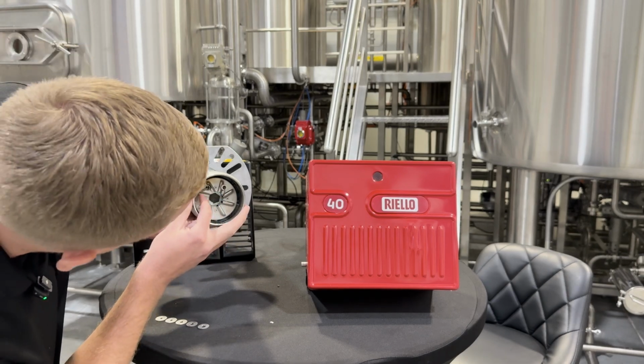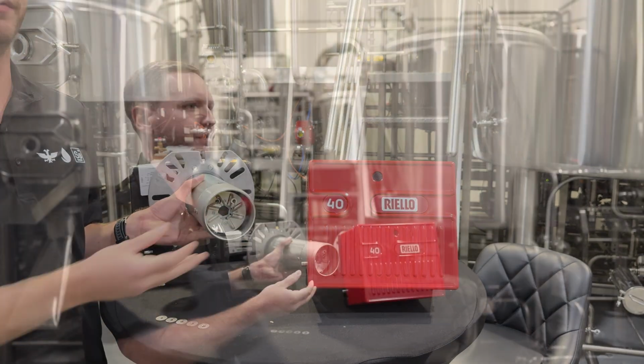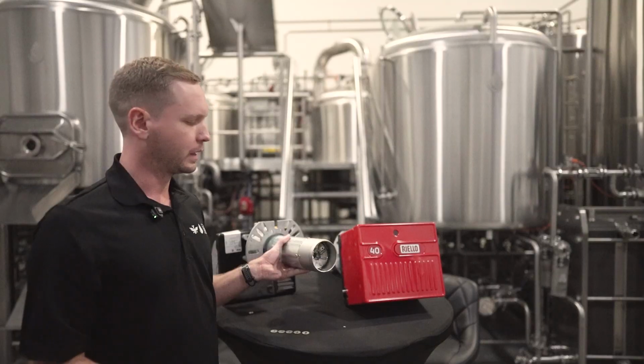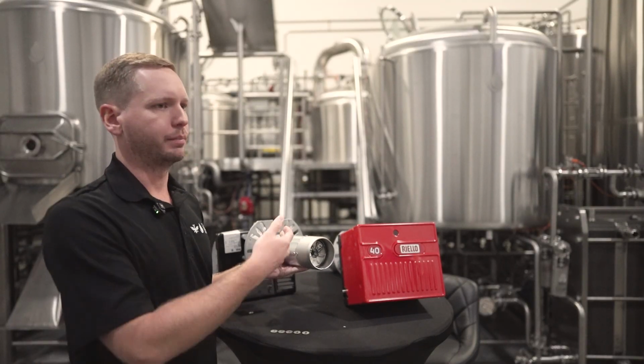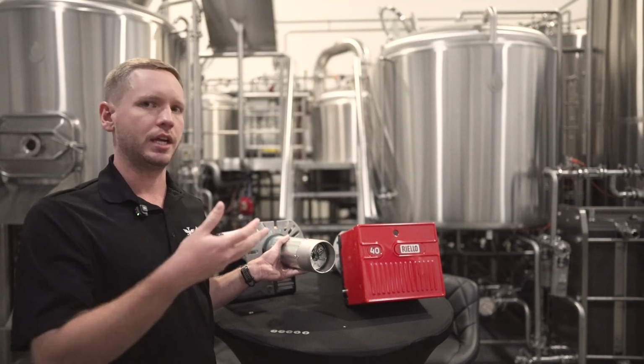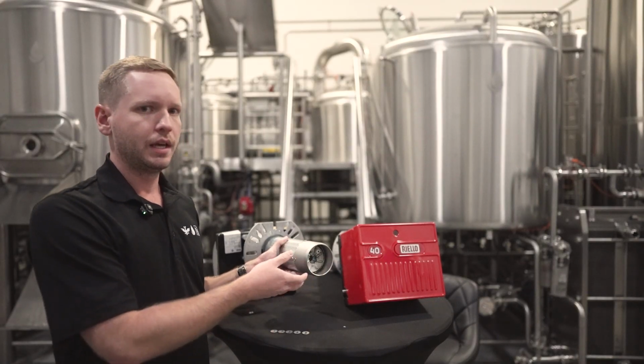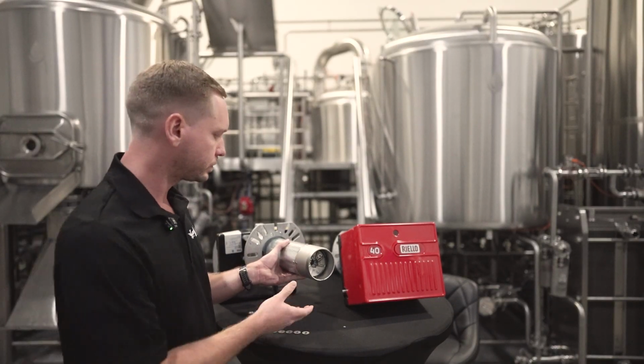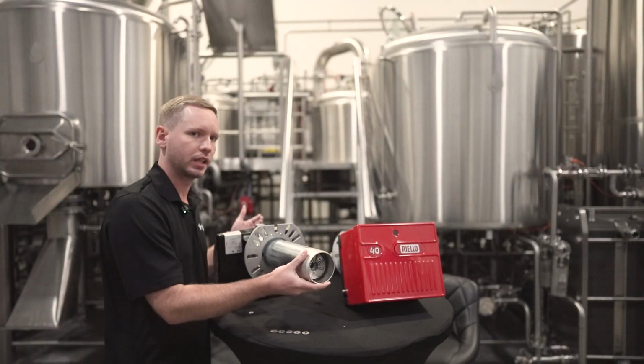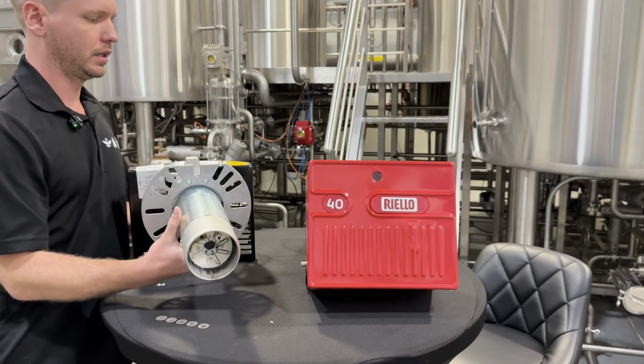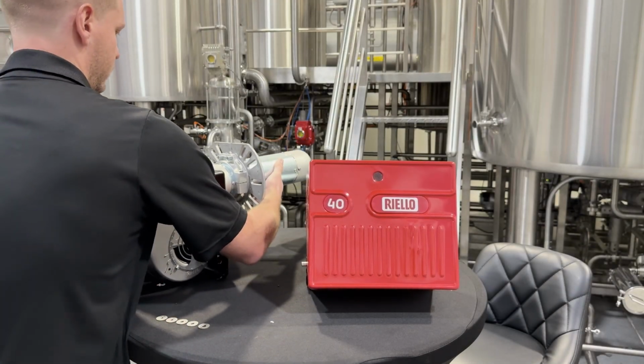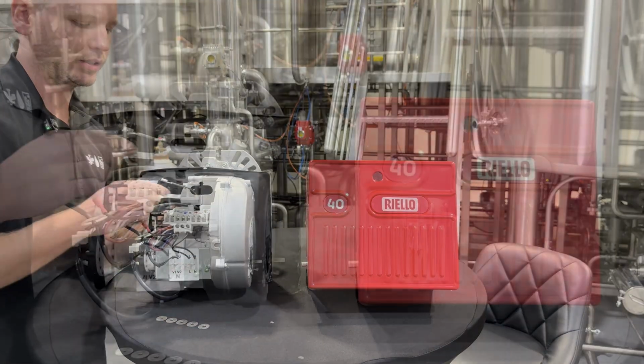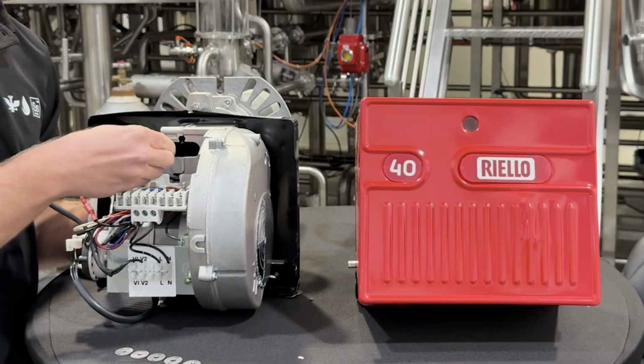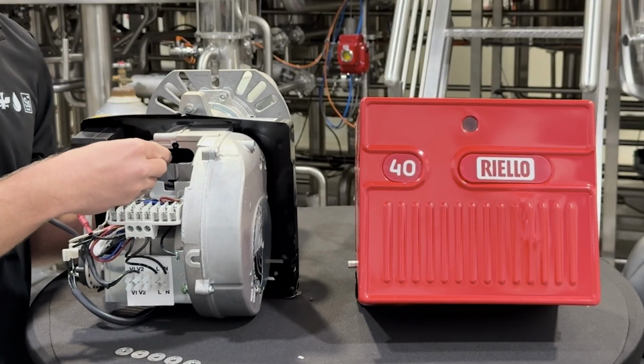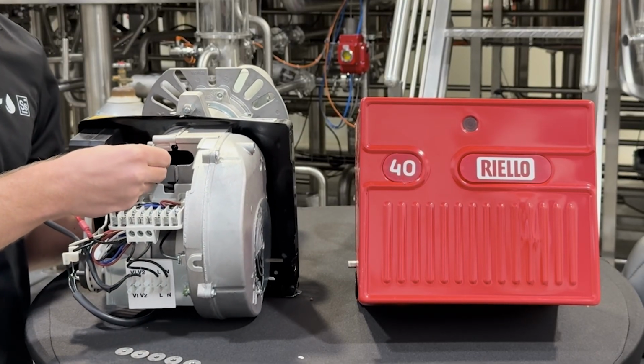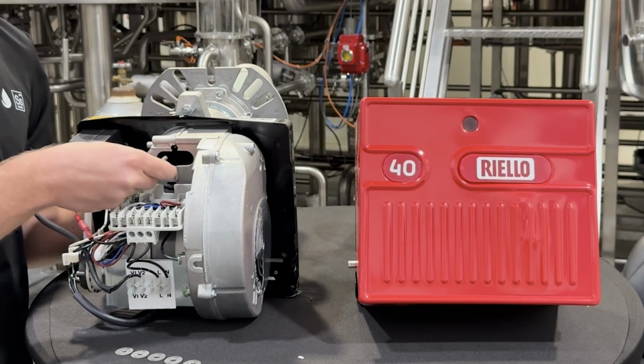And then we also have an ionization probe right here. That ionization probe is effectively measuring if a flame is present. Whenever a flame does go out, that ionization probe will know that something has changed in the air chemistry within this burner box, and it's going to turn off the whole system. So something to always check if you think it's electrical is get into the back of this. I'll flip this guy around. When you get into the back of this little probe right here, just make sure it's seated appropriately in that ignition probe. Just make sure that's seated and you're good to go.